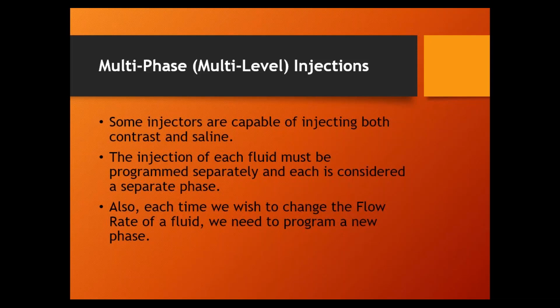This, a hold, if you hold something or you pause something, it sounds like the same thing, but it is slightly different. The difference between a hold and a pause, let's say phase 2, I want to program, let's say phase 2, that 4-phase injection I just showed. And let's say I want to program in a hold, right? I want to do phase 1, and when the first phase is finished, I want the injector to stop. Right? I don't want the injection procedure to end. I just don't want to inject right now. I want to hold the injection. Right? So an injection hold is a permanent stoppage of the injection until the operator hits the go button again. Right? That is a hold. Right? And it can last 20 minutes. And it won't go again until the operator hits the button, hits the start switch.